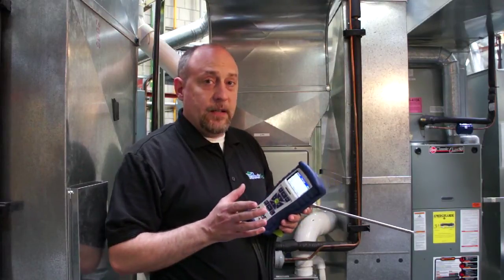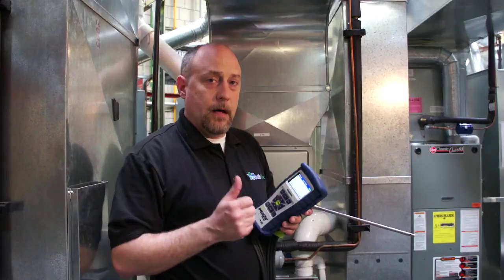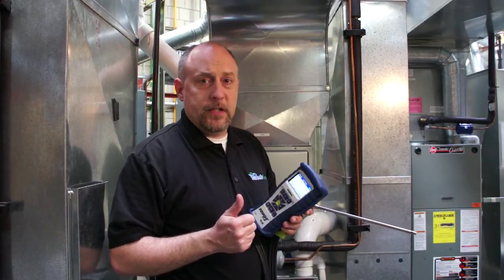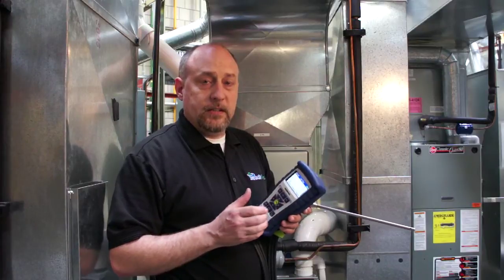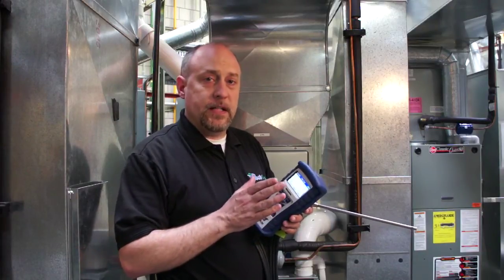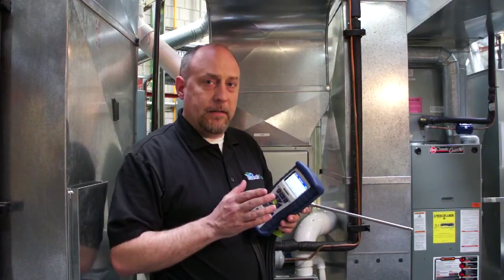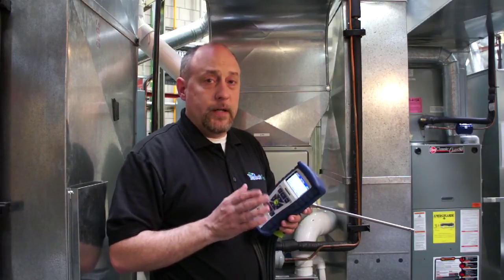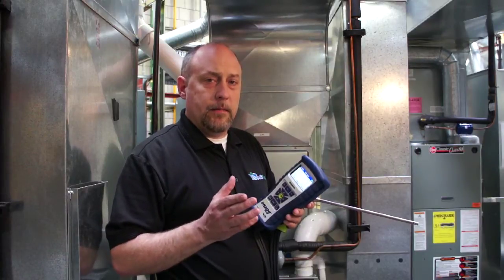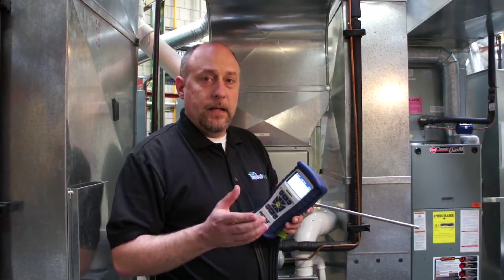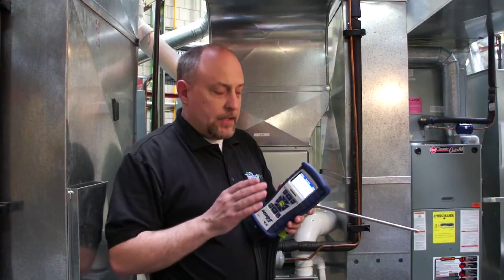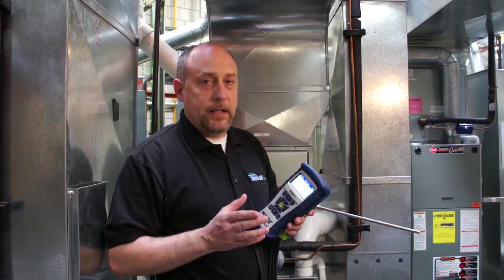Probably the key features on this thing that I want you to walk away with is that the Insight has a lot of really good productivity features, including the trend display where you can see things like peak CO or peak efficiency or anything else you might want to see a trend on. It also has the bar graph display with a go, no-go feature on there, which is really good for technicians when you really don't understand how all those things work together and how they're all intertwined. It allows the owner of the company to say, hey guys, I want you to set it up this way. And when you go out, if you see anything in the red, give me a call so I can come out and help you and make sure that we don't leave anything that wouldn't be safe for the consumer. That's a really good feature on this instrument, and it's something I think a lot of guys will get a lot of use out of.